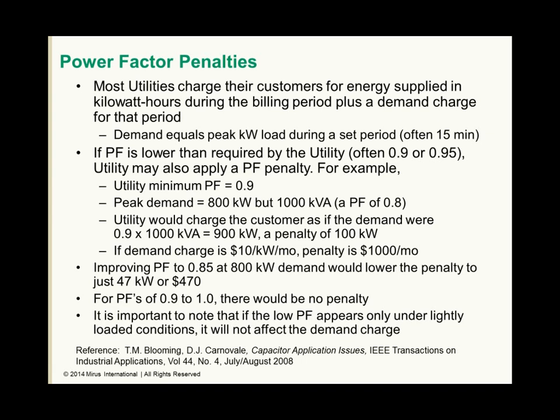Improving the power factor to 0.85 at 800 kilowatt demand would lower the penalty to just 47 kilowatts, or $470. This is because the 800 kilowatt demand divided by 0.85 power factor is 941 kVA, so the load would then only draw 941 kVA. If we take that 941 kVA and multiply it by the minimum power factor of 0.9, the resultant kilowatts is 847. So that's 47 kilowatts above the 800 that we're actually drawing. For power factors in the range of 0.9 to unity, above the minimum, there would be no power factor penalty. One important item to note here is that if the low power factor appears only under lightly loaded conditions, it will not affect the demand charge, because the demand charge, by definition, is applied when we're at peak demand load.